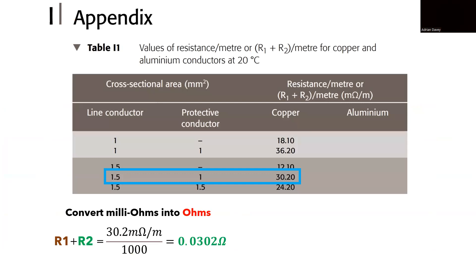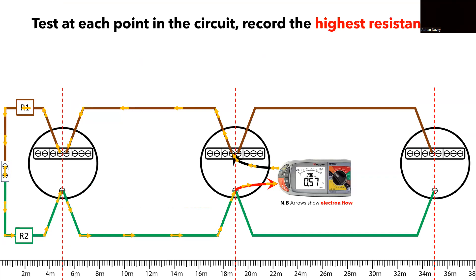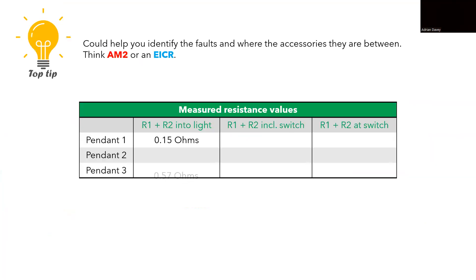Once again, we can cross-check the readings displayed on the meter to ensure their consistency with the expected values by referring to appendix I of the on-site guide. We are continuing to use twin and earth cable using a 1.5 mm-squared line conductor and a 1 mm-squared CPC, resulting in the same conversion to 0.03 ohms. Now, when we consider 19 meter distance from the previous slide, our calculation gives us an estimated reading of approximately 0.57 ohms. This further validates the reading we obtained for the second light on the supply side. We can now document this reading on our results table.